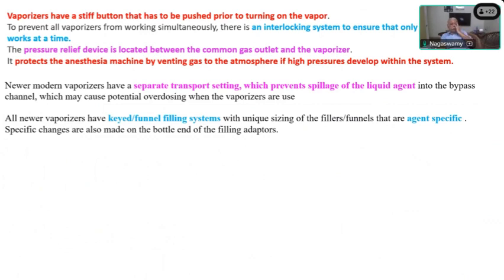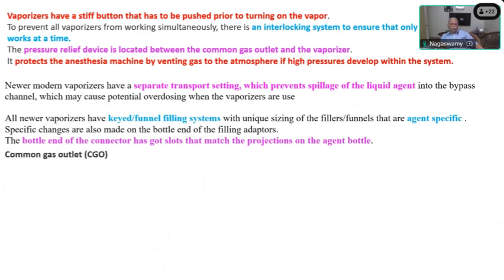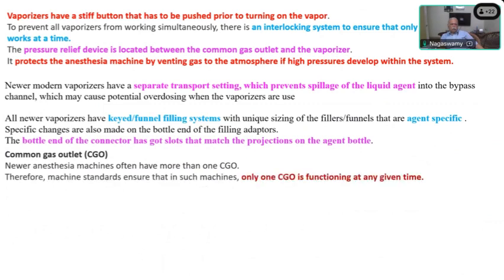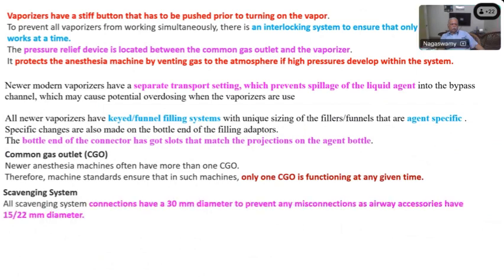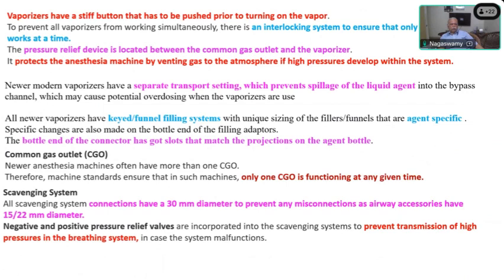And they have the keyed and funnel filling system, and they are all agent specific. These are also part of the safety features which you have to mention. The bottle end of the connector has slots that match the projections on the bottle. Then coming to the common gas outlet, newer machines have more than one common gas outlet, so the machine standards ensure that only one common gas outlet is functioning at any given time. Now coming to the scavenging system, all scavenging system connections have a 30 mm diameter so that you don't by mistake connect it to the breathing circuit. These are larger diameter connectors, and they have negative and positive pressure relief valves incorporated into the scavenging system to prevent transmission of high pressure into the breathing system.